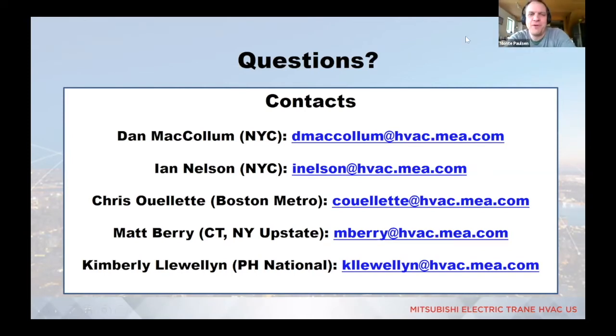Hey, great to see you all. I'm going to ask just a couple questions about the hybrid system. I'm trying to get a sense of how the distribution would split between the VRF distribution and the hydronic distribution. Would you need one of those sub boxes every floor, every couple of floors? Do you have a sense of how many units per breakout box would happen if we're talking about low load units? So I can tell you that we anticipate the largest hybrid BC controller having 16 zones.